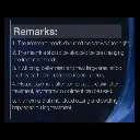Set frequency and energy, then launch the machine. Keep the handpiece aimed at the treatment skin uprightly and treat with the focused laser beam. The patient will normally feel mild tingling. Remarks: do not screw the treatment head too tight; stop the machine before changing heads; treat large area tattoos part by part from outside to inside; apply erythromycin ointment after treatment; mild bleeding and swelling during treatment are normal.